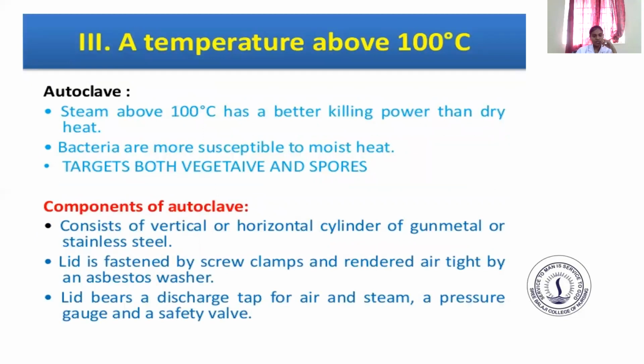And then third one, temperature above 100 degrees centigrade. In the autoclaving method, steam above 100 degrees centigrade has a better killing power than dry heat. Bacteria are more susceptible to moist heat. Components of an autoclave consist of a vertical or horizontal cylinder of gunmetal or stainless steel. The lid is fastened by screw clamps and rendered airtight by an asbestos washer. The lid bears a discharge tap for air and steam, a pressure gauge and a safety valve.